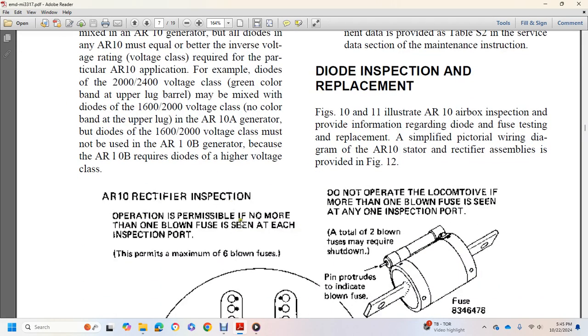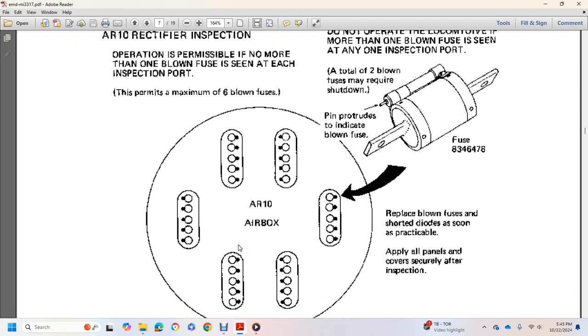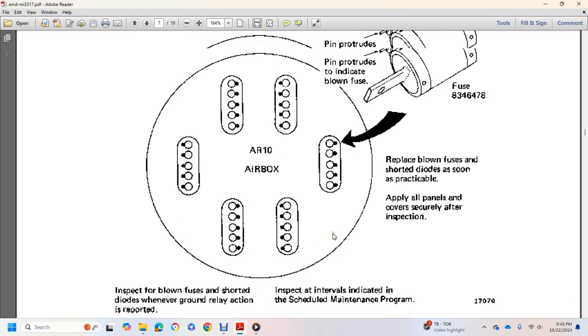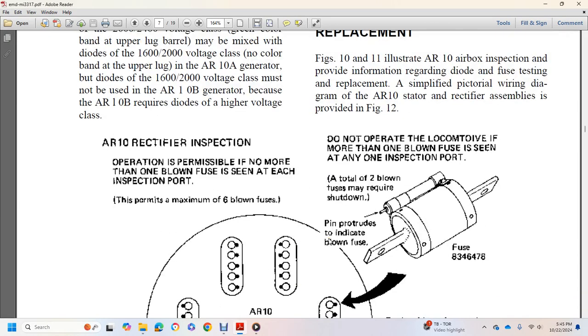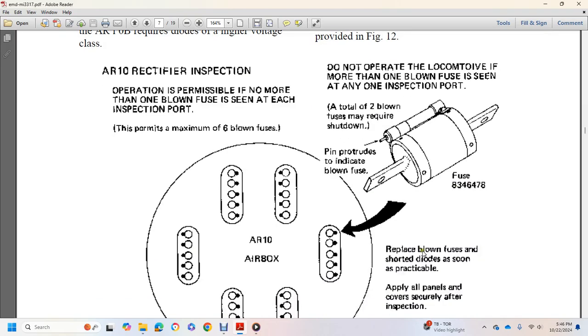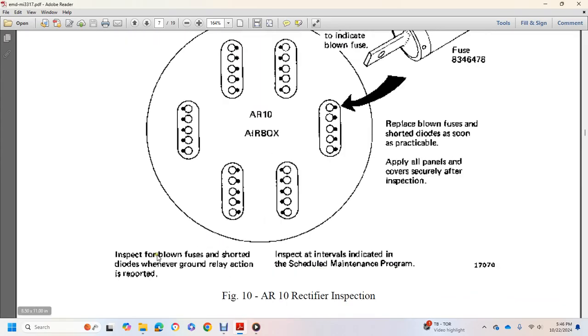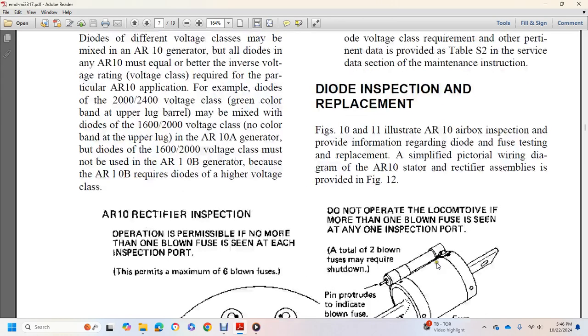AR10 rectifier operation is permissible with no more than one blown fuse seen at each of the inspection ports, maximum 6 blown fuses in the AR10 airbox, total 2 blown fuses required with the shutdown pin protruding with the indicated blown fuse. Replace the blown fuse and shorted diode soon, with all panels covered securely after inspection. Inspect for blown fuses and shorted diodes whenever ground relay action is reported. Inspect at the intervals indicated in the scheduled maintenance program.